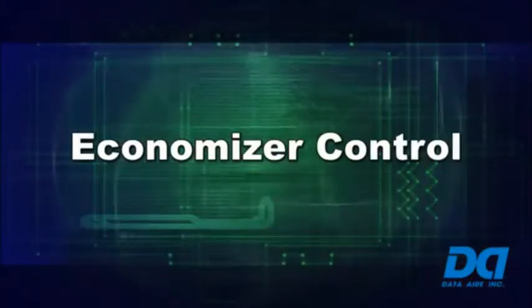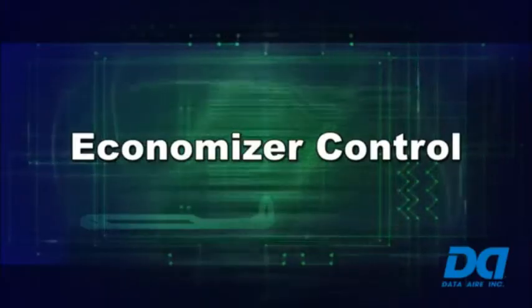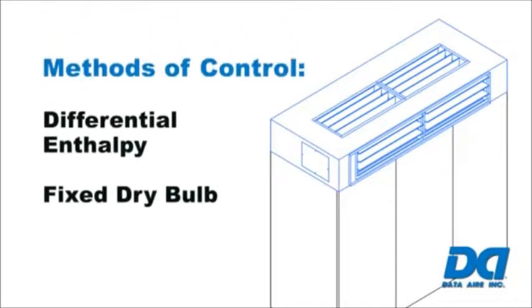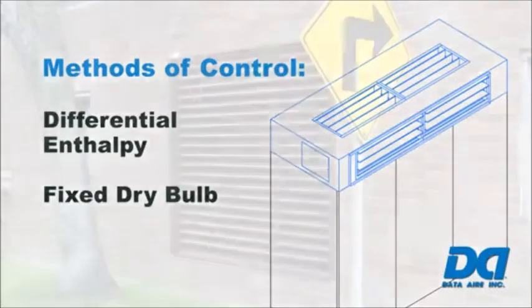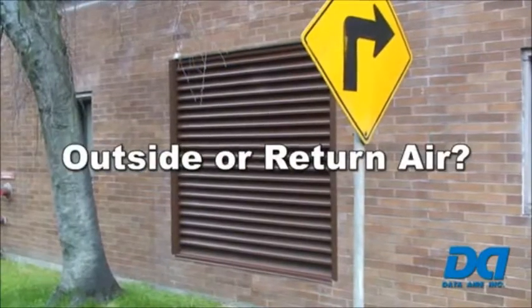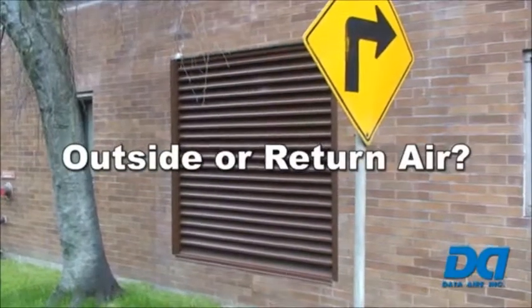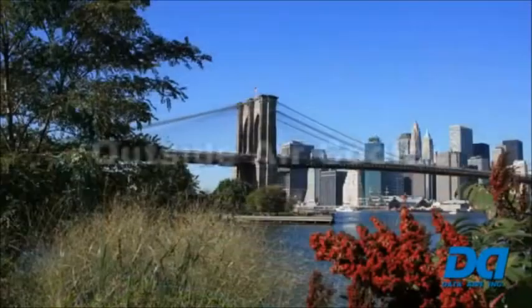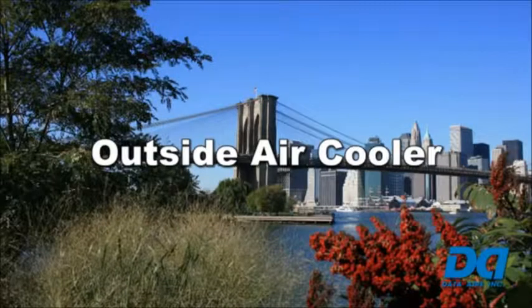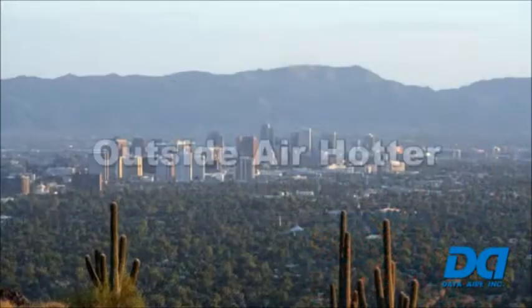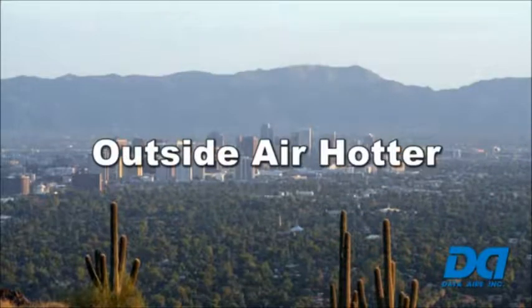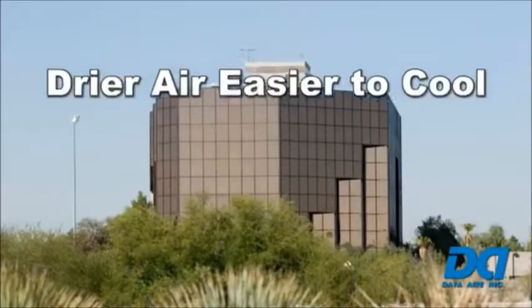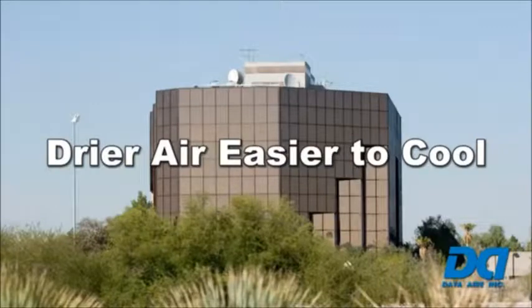Aire provides two methods of determining how to control the economizer: differential enthalpy or fixed dry bulb method. The differential enthalpy method, enthalpy being the measure of the total energy in the air, determines whether the outside air or the recirculated return air is more efficient to cool. This could occur when the outside air is cooler than the return air, or even if the outside air is hotter but drier than the return air. Drier air is easier to cool than air with more moisture, resulting in less energy consumption.